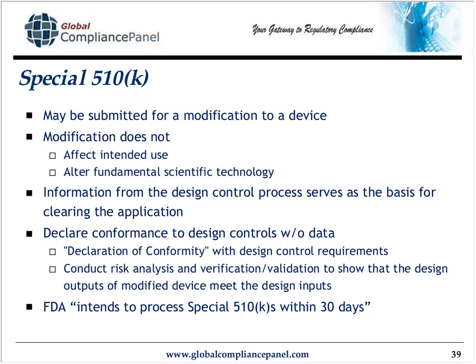That's the information you're providing. It's okay to declare conformance to design controls without providing the data. You're going to provide a declaration of conformity. You're certainly going to have conducted a risk analysis to show that the design outputs meet the design inputs. And FDA certainly intends to process special 510Ks in 30 days, but I intend to do a lot of things I don't do also.